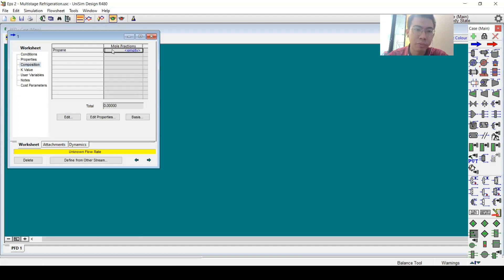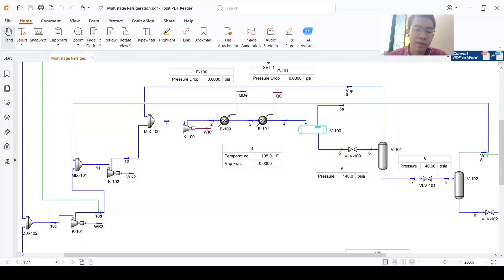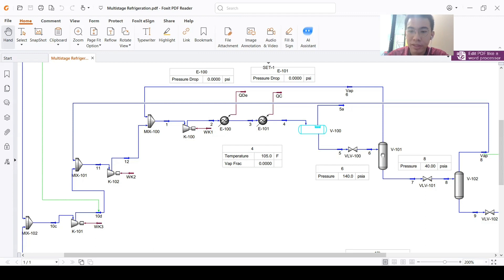Now let's start with stream number 1. The composition is of course only propane — you can try other refrigerants later, but in this video I will use a propane refrigeration system. The next step is determining the pressure or temperature. We don't have direct information for stream 1, but stream 6 gives us a clue: the pressure at stream 6 is 140 psi.